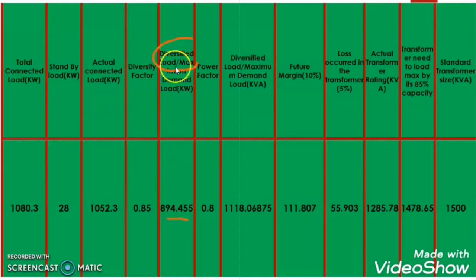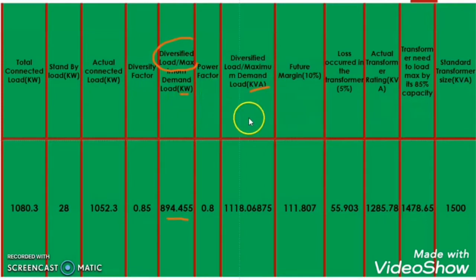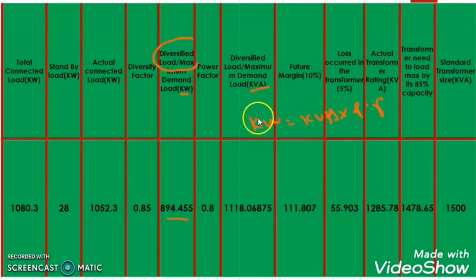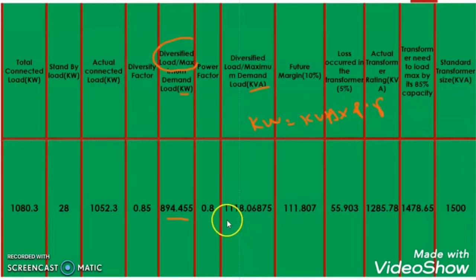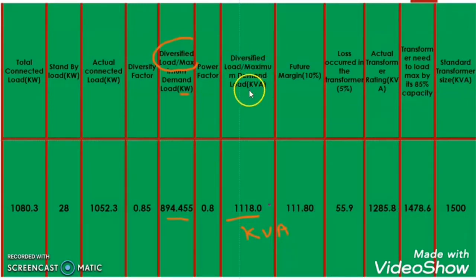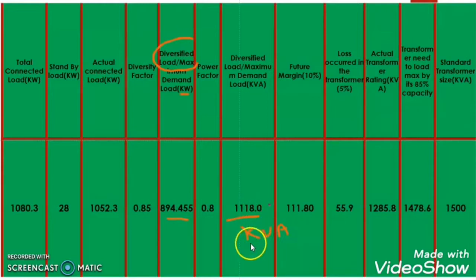Now I want to calculate this diversified load not in kW but in kVA. The formula is: kW is equal to kVA into power factor. So the kVA value will be kW divided by power factor. So our diversified load in kVA becomes 1118.07 kVA — approximately 1118 kVA.